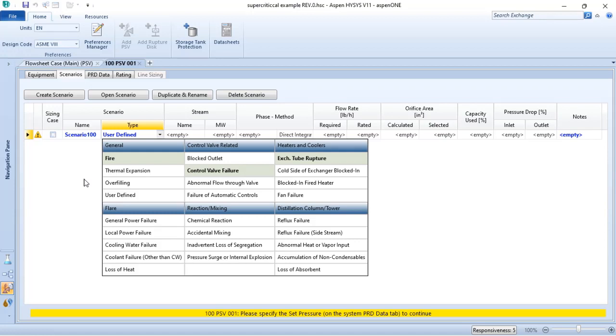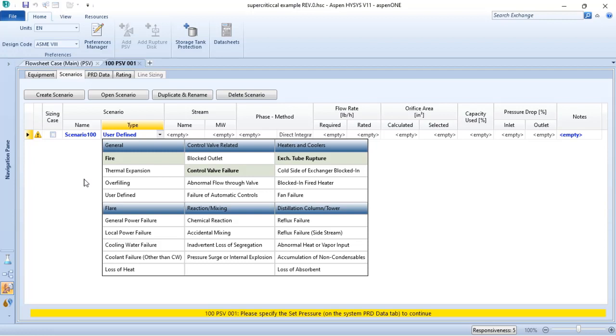So here you can see that, for instance, fire is a scenario where you can have overpressurization of your system, because if you keep adding heat to a vessel, the fluid that's inside the vessel will expand and with that increase the pressure until it reaches the maximum allowable working pressure of the equipment, or you relieve the amount of fluid inside to prevent overpressurization.